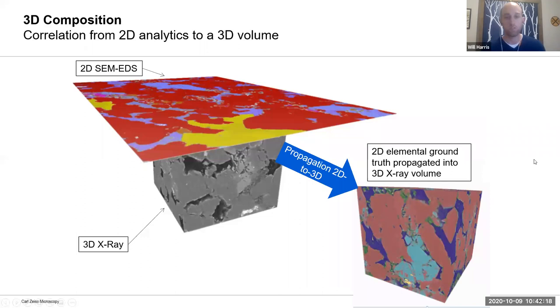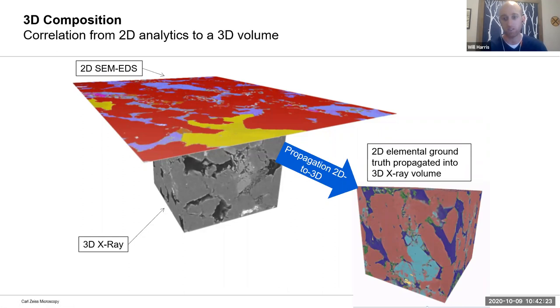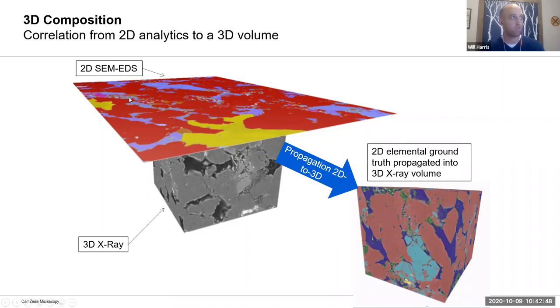We've started doing some pretty exciting things about three or four years ago, initially in the geosciences but propagating more broadly: correlating data between different methods. Specifically, looking at 3D x-ray data combined with elemental data from a technique like EDS within a scanning electron microscope. If you have a common surface, you can correlate a 2D plane with a single slice of the 3D volume and use clever algorithms to propagate that elemental or compositional information into your 3D volume — essentially mimicking a 3D EDS approach in a non-destructive way.